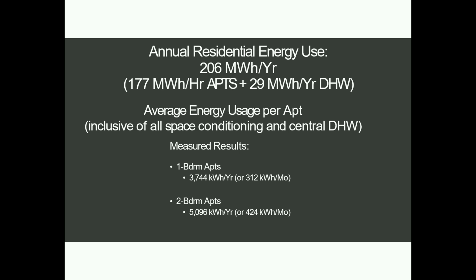This was the average electricity used per month: about 312 kilowatt hours per month for a one-bedroom, about 420 for two-bedrooms. You know what the average is for non-electrified buildings? It's about 600 kilowatt hours per apartment on average in New York State. So after electrifying a building, we used less electricity than the average non-electrified building uses, which is on gas for hot water and for heating. Think about that. That means we can make this entire transition with less energy rather than more. That's if you design it correctly.